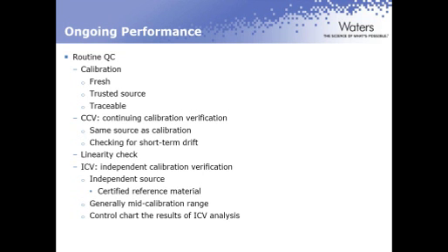You can also do linearity checks. How high can my method go? Am I still linear through a certain concentration range? Use what's called an independent calibration verification, or an ICV. These are made from sources independent from the one that your calibration and your continuing calibration are made from. Okay, certified reference material, again, is a prime way of accomplishing this particular task.